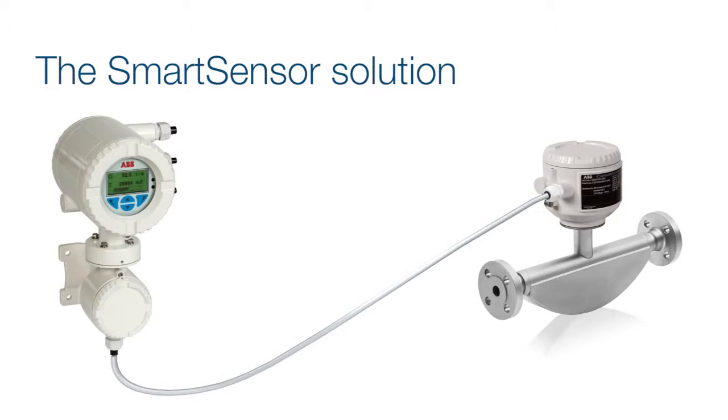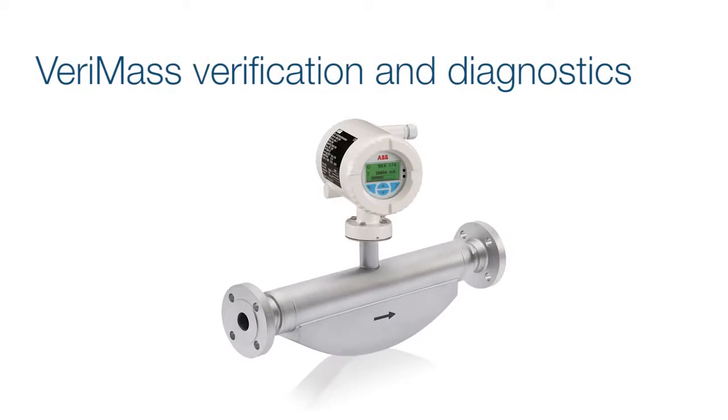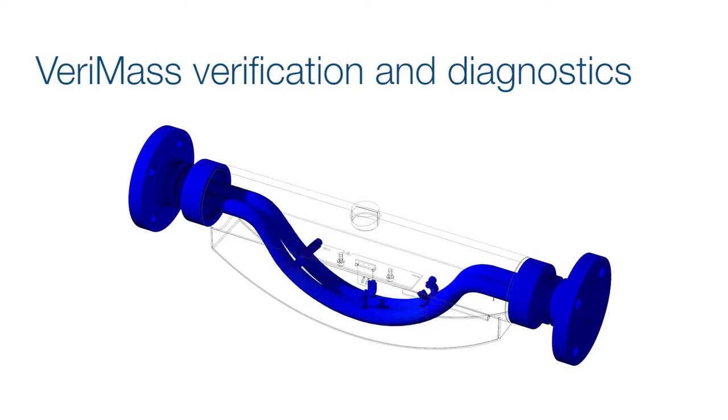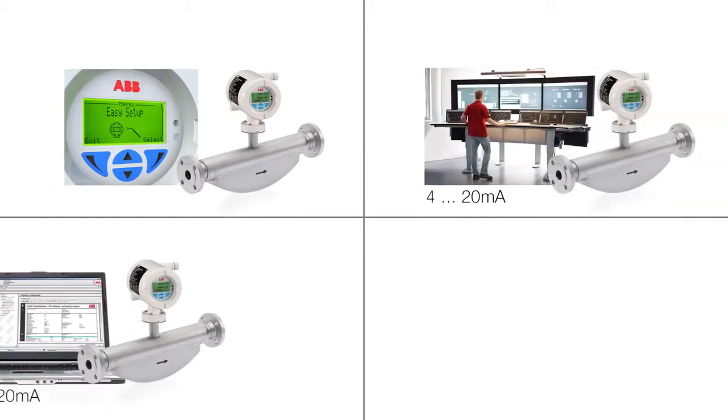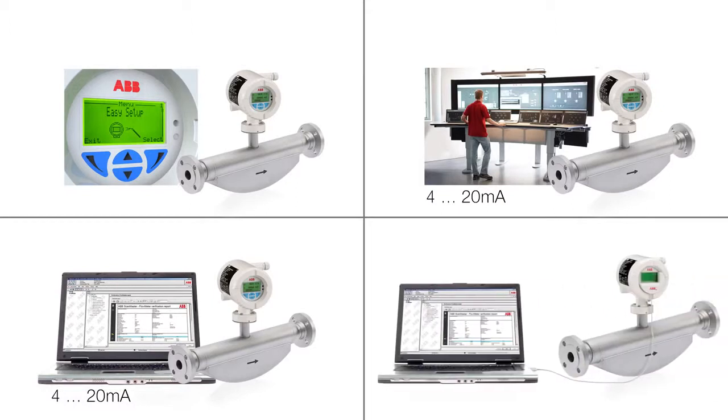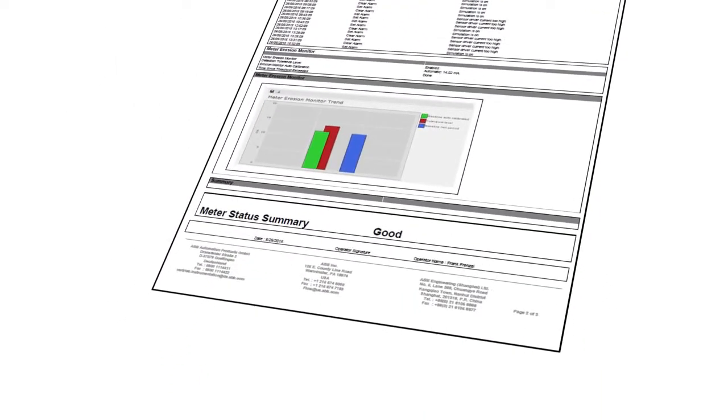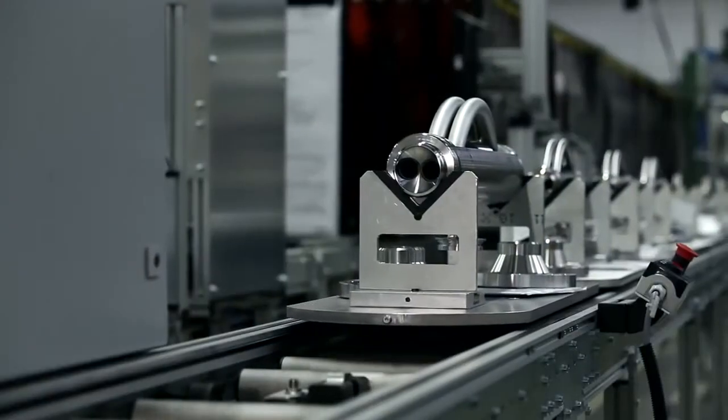The integrated verification diagnostics detect possible tube erosion or coating affecting meter accuracy. It can be operated through the local display, the control system, or PC. With the ABB local adapter, the PC can be connected without the need to open the housing. The verification report summarizes the meter status and shows meter trends.